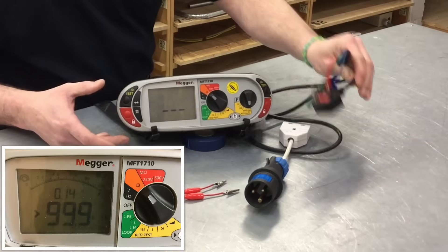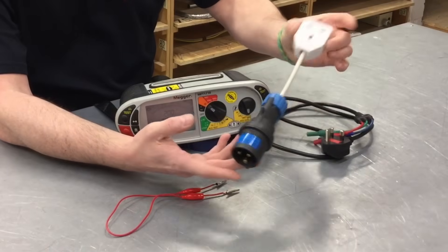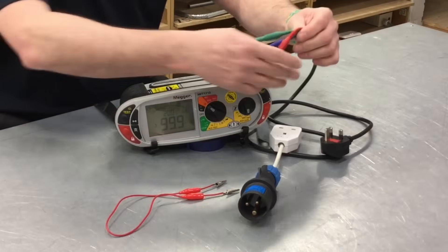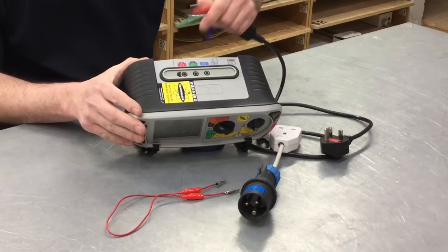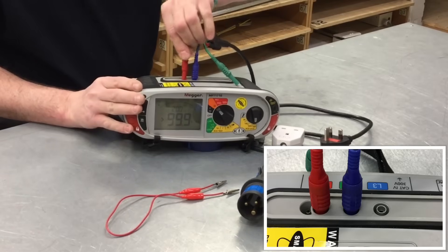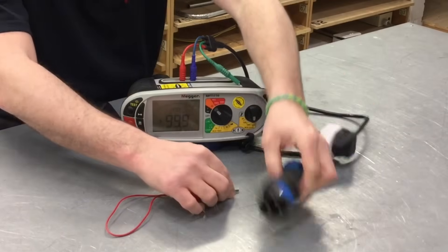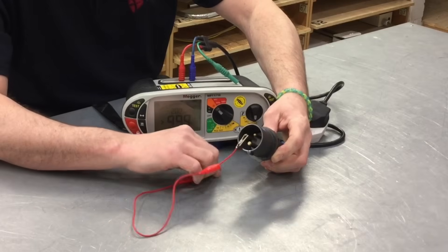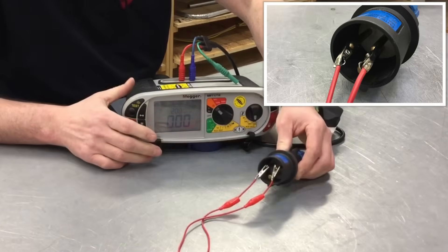We're going to need to remove the resistance of both the plug-in lead that came with the Megger MFT and our modified 16 amp plug top with a 13 amp plug top adapter as well. So first of all, between line and neutral, we take the red and blue connections and go into the red and blue section in the top of the Megger MFT. We plug them together and link together at the very end, linking together the line and neutral.